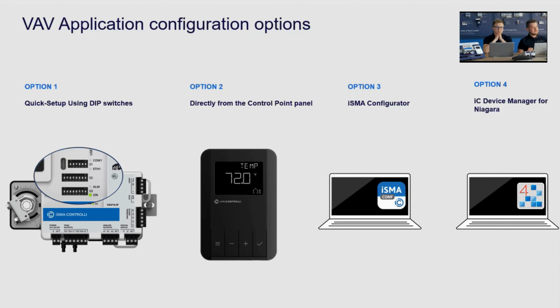The second option is the dedicated wall operating unit we call control point. The control point gives you an option, next to being a space sensor with 3 sensor types, to freely configure the VAV application directly from the panel when it is connected one-to-one to the controller, or through the built-in USB port in the wall unit.